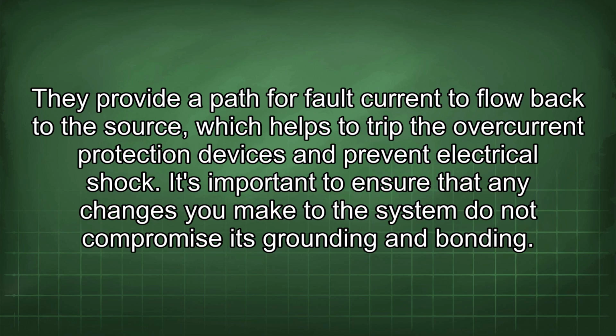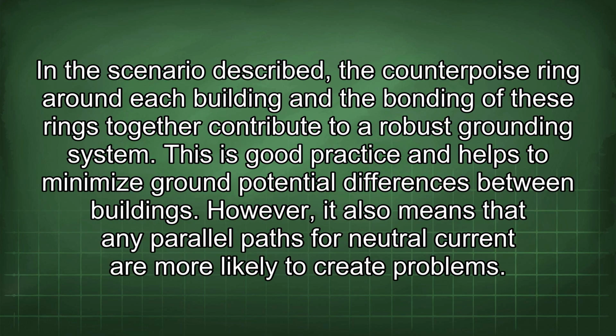It's important to ensure that any changes you make to the system do not compromise its grounding and bonding. In the scenario described, the counterpoise ring around each building and the bonding of these rings together contribute to a robust grounding system. This is good practice and helps to minimize ground potential differences between buildings. However, it also means that any parallel paths for neutral current are more likely to create problems.